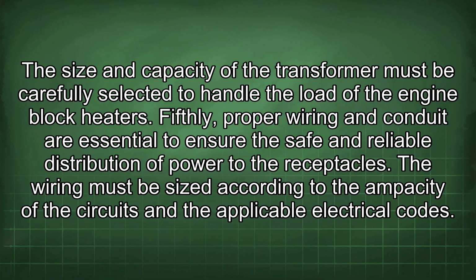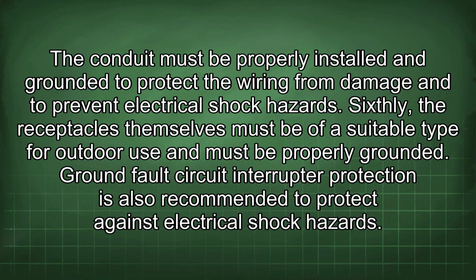Fifthly, proper wiring and conduit are essential to ensure the safe and reliable distribution of power to the receptacles. The wiring must be sized according to the ampacity of the circuits and the applicable electrical codes. The conduit must be properly installed and grounded to protect the wiring from damage and to prevent electrical shock hazards. Sixthly, the receptacles themselves must be of a suitable type for outdoor use and must be properly grounded.